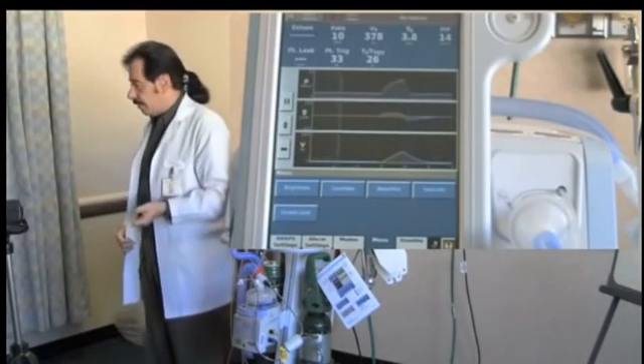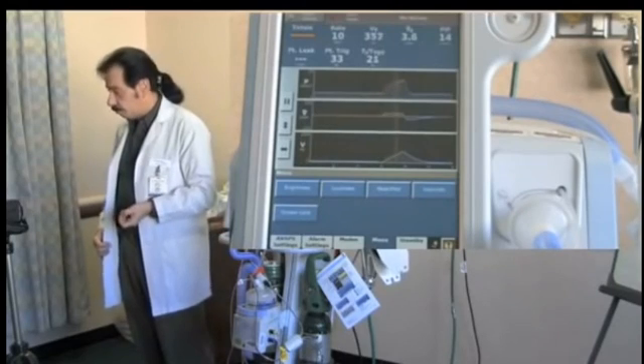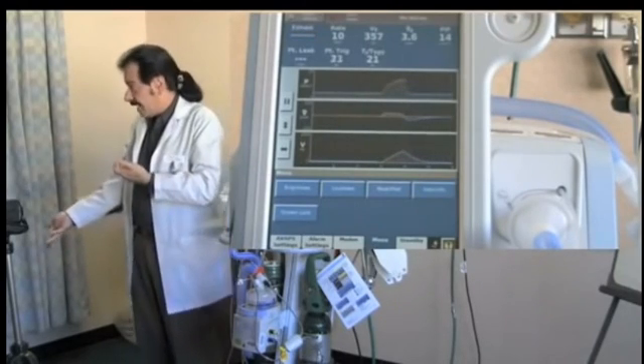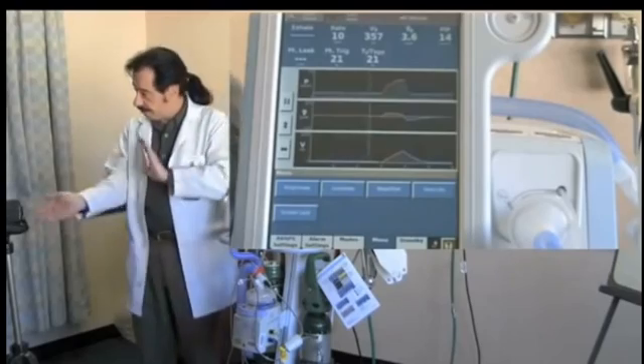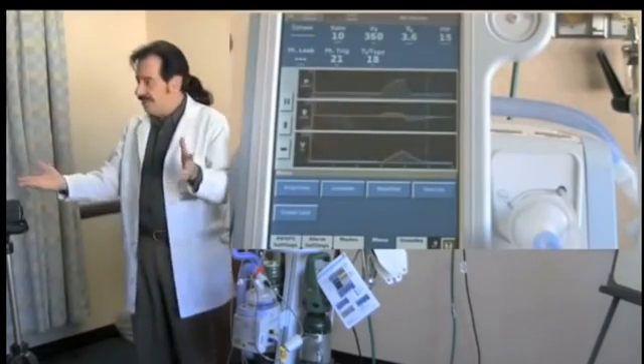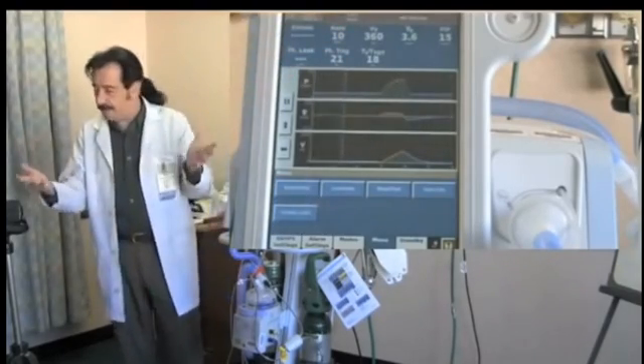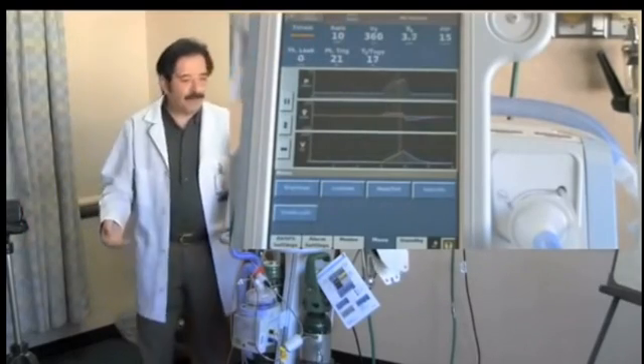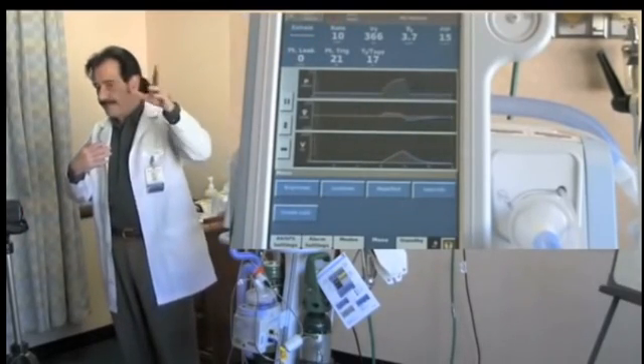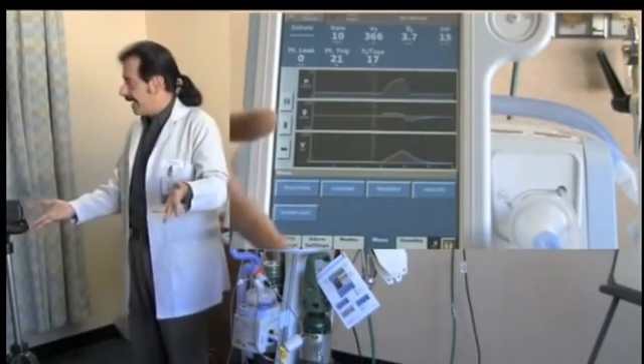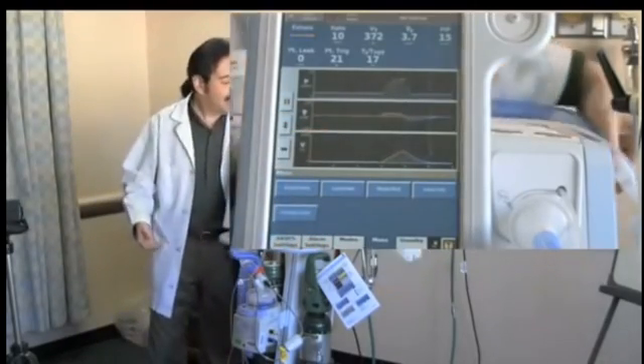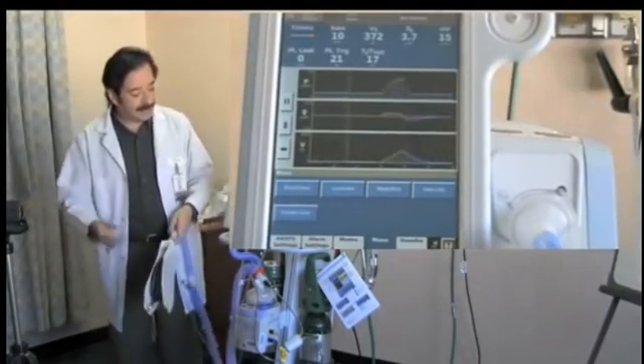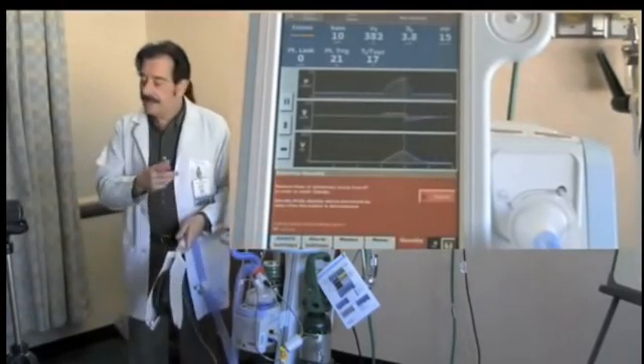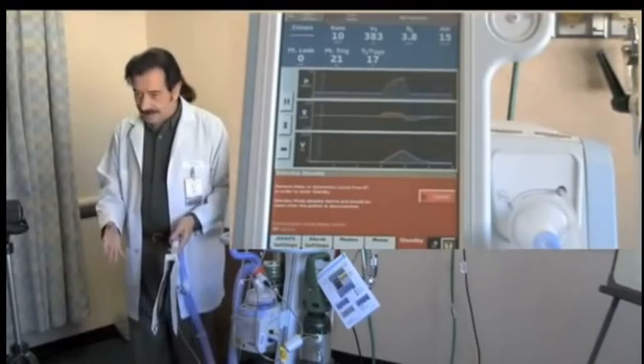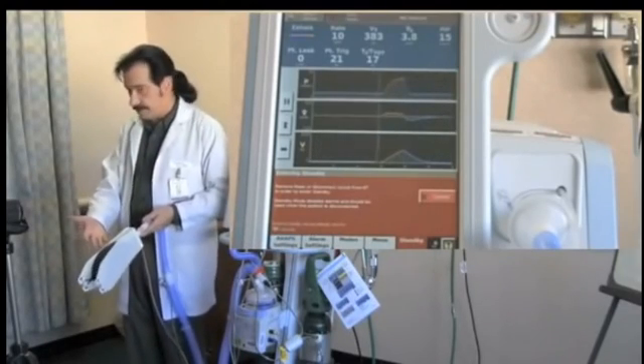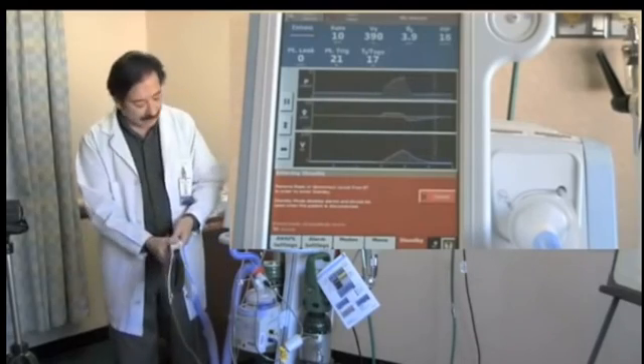Now the standby mode in the Vision was pretty clunky. It often would fall out of standby and start alarming, and the nurses would unplug it and shove it over in the corner, and you say, "Hey, why'd you turn my machine off?" Because it was alarming. We couldn't make it stop. If you just walked by a room and glanced in there and looked at the circuit funny, it would fall out of standby and start alarming. Okay? So they've improved that in the V60. I press my standby button. The V60 says, I'll be glad to go into standby, but not as long as you've got a patient connected to it. Okay? And it can detect that there's a patient there.